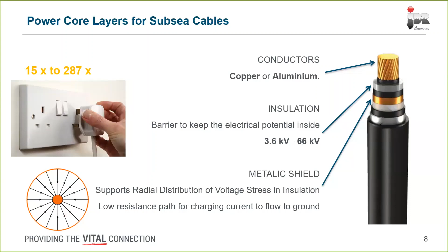In terms of insulation, that's sized based on the voltage we're going to carry. The majority of cables supplied at the moment are within the region of 33 kV, but we've developed cables capable of carrying up to 66 kilovolts, which is just shy of 300 times what you get out of your socket at home - staggering quantities of energy. You'll also have a metallic sheath as a basic component of the conductor, ensuring electrical stresses are uniformly distributed radially around the conductor within the insulation.